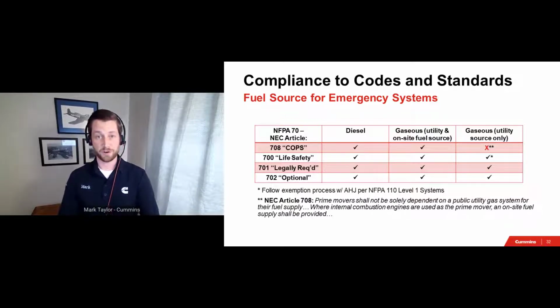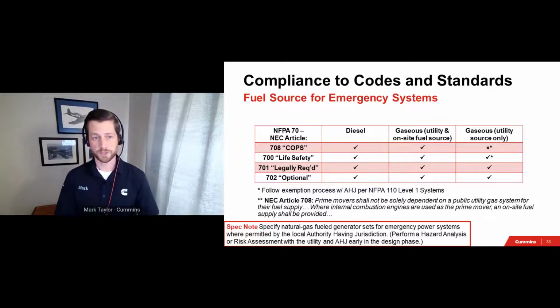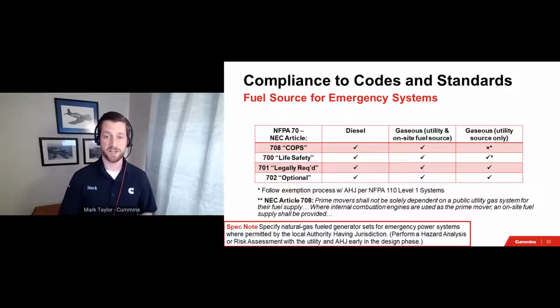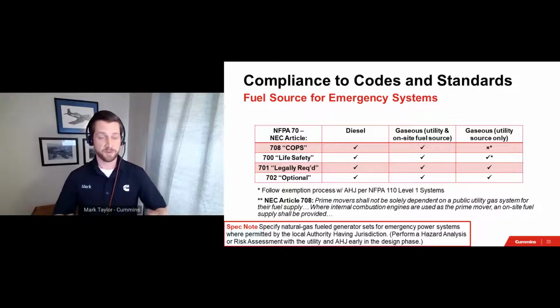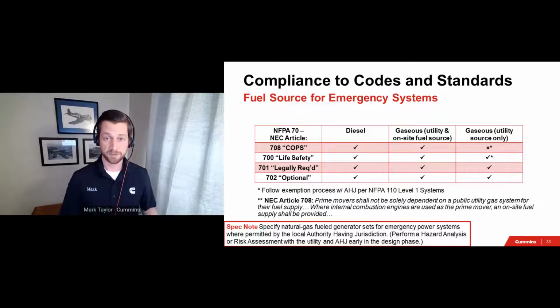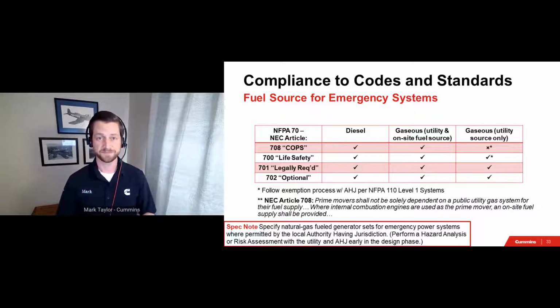Finally, I'll note here that Article 708, Critical Operations Power Systems, does contain language that actually explicitly requires on-site fuel storage for combustion engine-driven generator sets. So there's no way out in that case. So in some scenarios, solely relying on the utility may be a more nuanced conversation with the AHJ. But those are conversations that happen frequently, and relying on the utility as the sole source of fuel can be very reliable as a means of fueling a generator set.